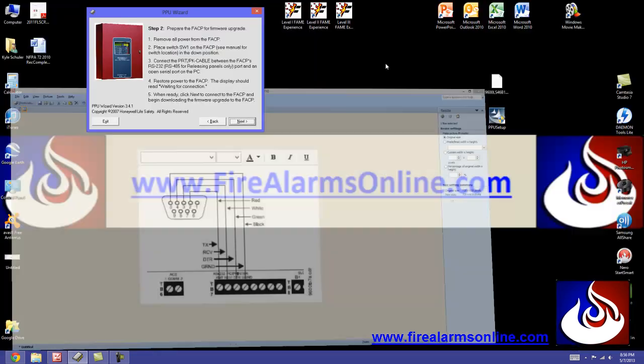So once you have your cable connected, switch SW1 in the down position, restore power to the FACP, and the display is going to show waiting for connection. When you're ready, click next. Obviously, like I said, I'm not connected to a panel, so I'm not going to take you much further than this step.